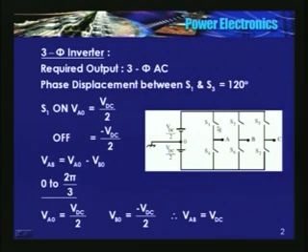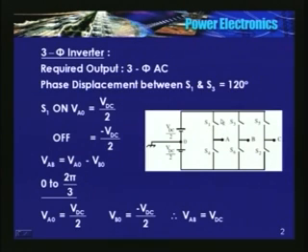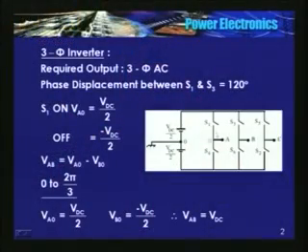I have shown the switching elements as S1, S3, S5, S4, S6, and S2. I have not shown an anti-parallel diode across the switch. In any VSI, S1 implies a controllable device and an anti-parallel diode connected across it. I told you that the switching signals for S1 and S4 are complementary. Similarly, S3–S6 and S5–S2, whereas switching signals for S1 and S3 are displaced by 120 degrees.